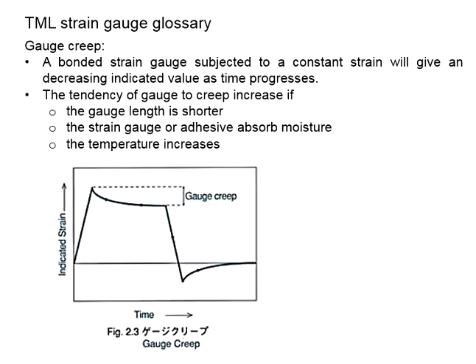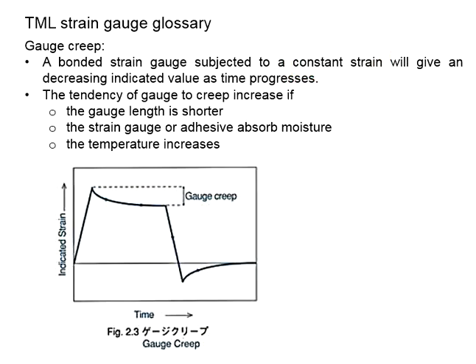However, what was actually happening is that the indicated value reduces over time, reduces further, and it goes back to zero strain. This is even though the constant strain still remains within the specimen. In this case, what was indicated by the strain gauge does not fully represent the actual situation of the specimen. This will affect the results.